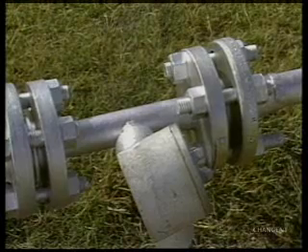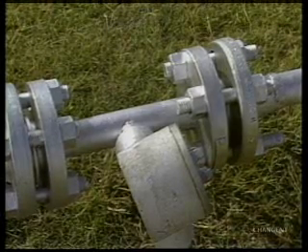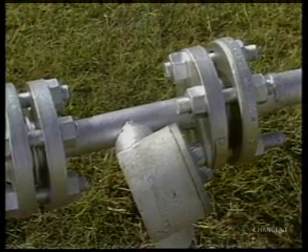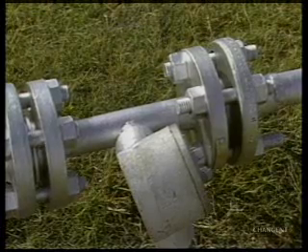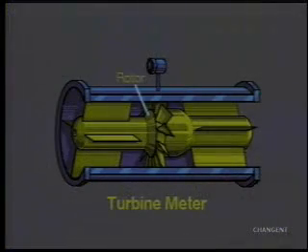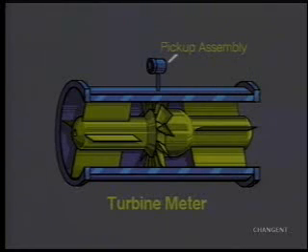Turbine meter construction is relatively simple. The meter itself is installed directly in the meter tube. The meter is a precisely balanced, free-running rotor mounted in a cylindrical housing, similar to a flanged pipe. This unit is mounted on the pipe's center line. A magnetic pickup assembly is positioned as close to the rotor as possible but does not penetrate the housing.